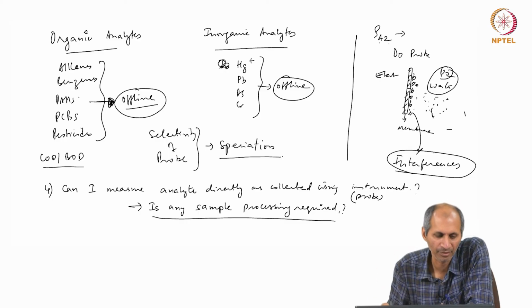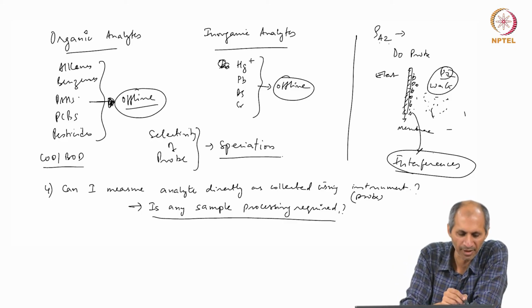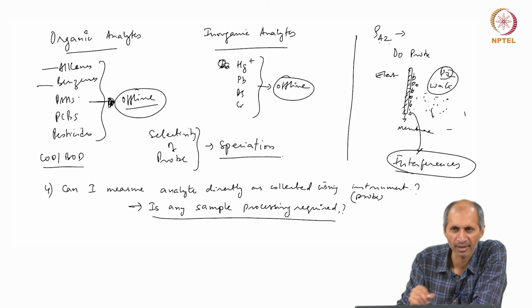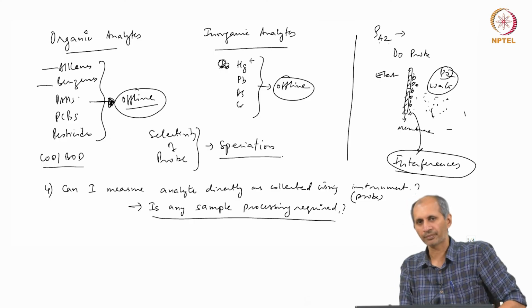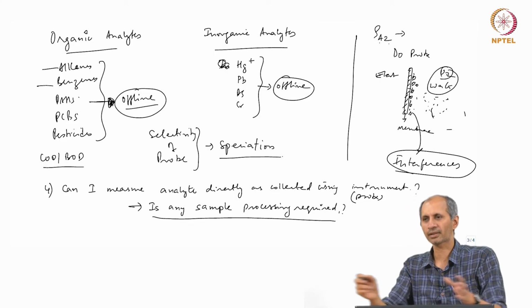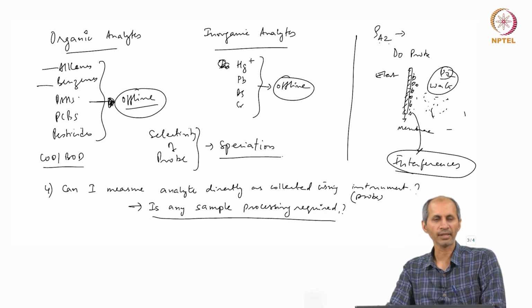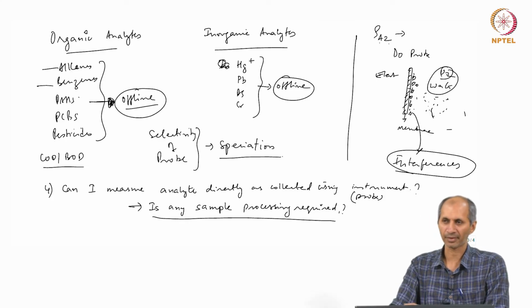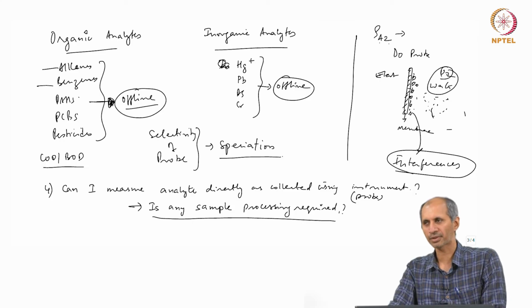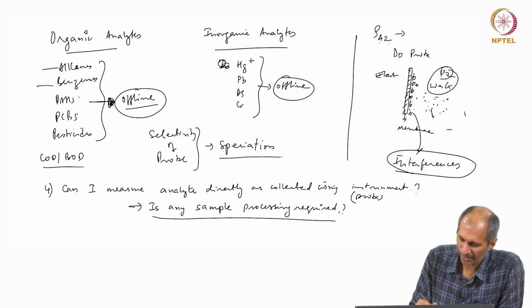advanced analysis of organics. For example, you have different classes, so you have alkanes and aromatics. A large amount of alkanes are, say, oils and things like that. If you have a lot of one class of compounds, it will interfere with the analysis of another class of compounds. We will see that when we do the mixture analysis. So, one has to look for interferences, and sample processing is required for interference.